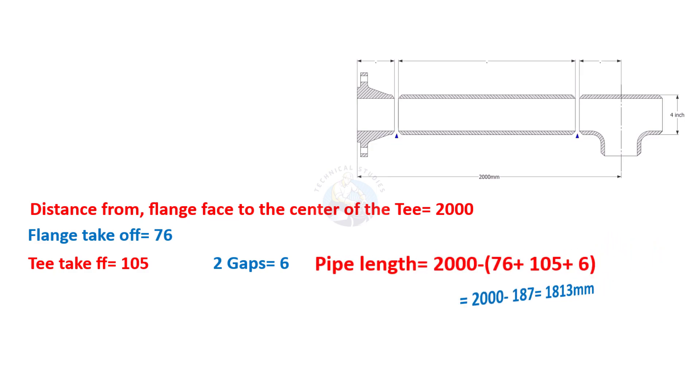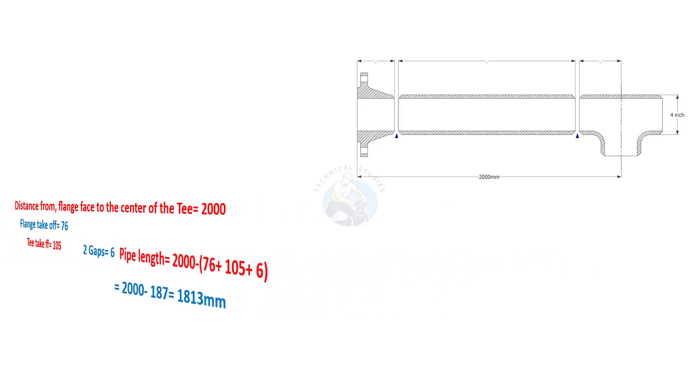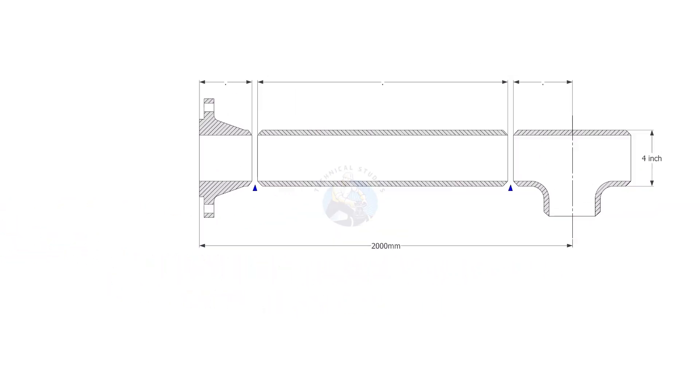Let us calculate. Add the flange takeoff, T takeoff, and the two gaps, then subtract the sum from the total length as shown. The required length of the pipe is 1813 millimeters.